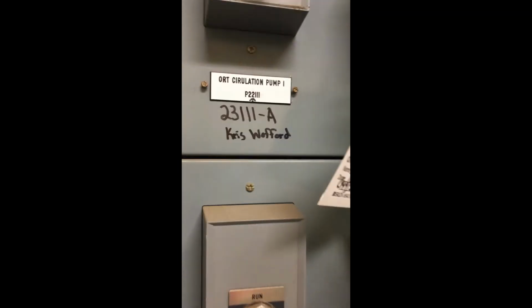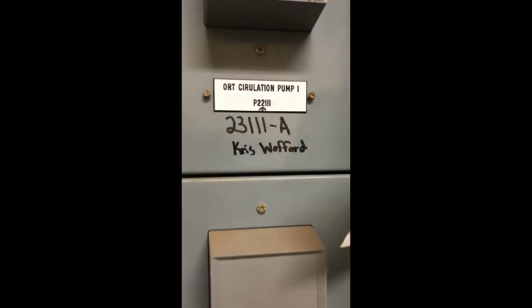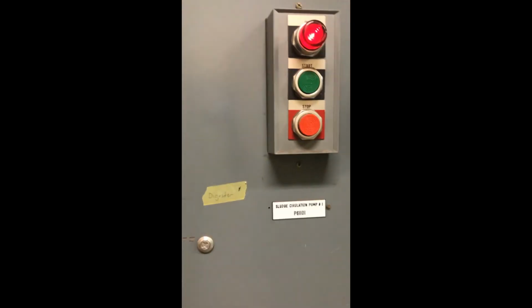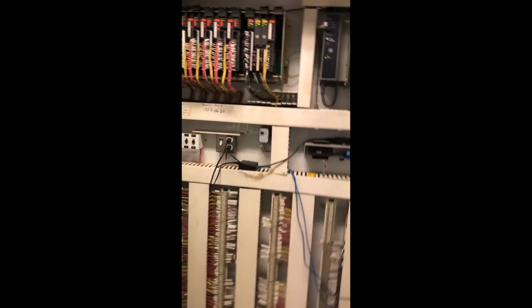Over here is where we have a lot of our ORT. ORT stands for odor reduction tower. We've got circulation pumps, an ORT supply fan. This is also where all the grit pumps are, the controls. This is where the PLC is for this side of the plant, for the influent pump station. This PLC controls the bar screens, or actually monitors them. They have their own controllers. Same thing, basically. The PLC is located in this rack. I/O, more remote I/O, field wiring, and then over here, some more I/O.